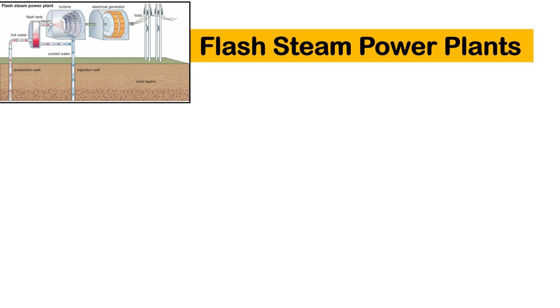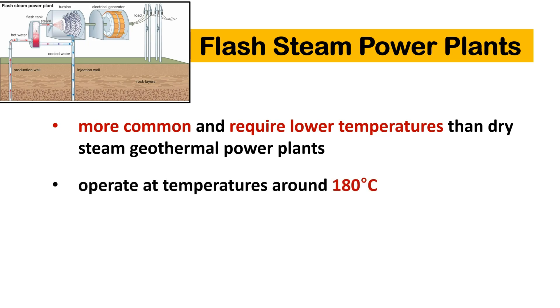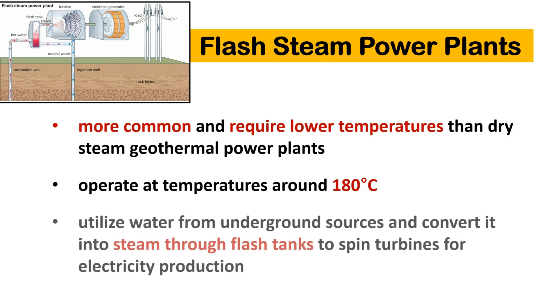Flash steam power plants are more common and require lower temperatures than dry steam geothermal power plants. These geothermal power plants operate at temperatures around 180 degrees Celsius. They utilize water from underground sources and convert it into steam through flash tanks to spin turbines for electricity production.